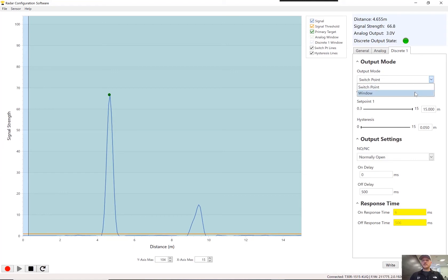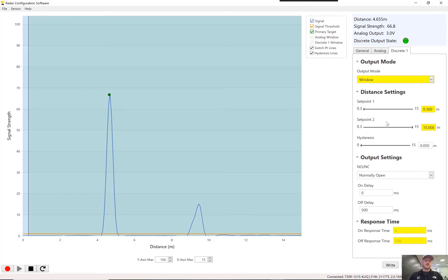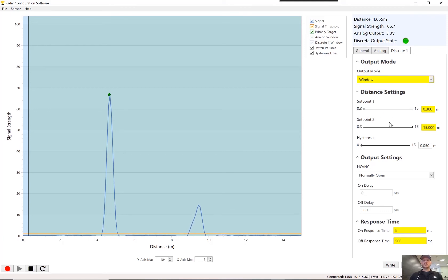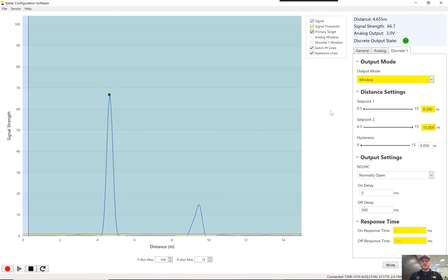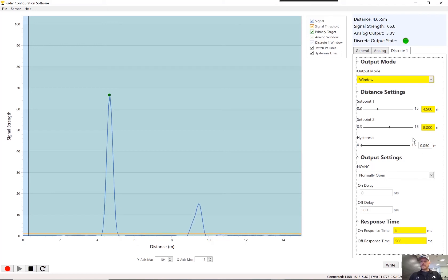And what we can do with this is you could have like a sort of put the sensor in a retro reflective mode with this. If you have a back wall that you're reflecting off of and you can set your threshold levels in sort of a window, which is kind of what we're going to do here. And that I want the output to be on when I'm between 4.5 meters and say 8 meters. And then we'll leave that normally open.